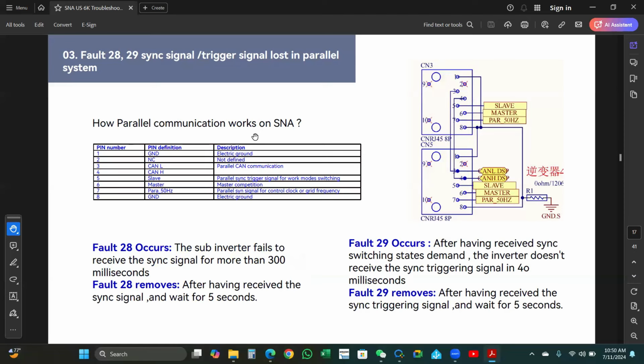Number three, faults 28 and 29: sync signal and trigger signal loss in parallel system. This is how parallel communication works on the SNA. Usually it is the Ethernet cable or the communication cable pinout. Fault 28 occurs when the inverter fails to receive the sync signal for more than 300 milliseconds. Fault 28 is removed after receiving the sync signal and waiting for 5 seconds.